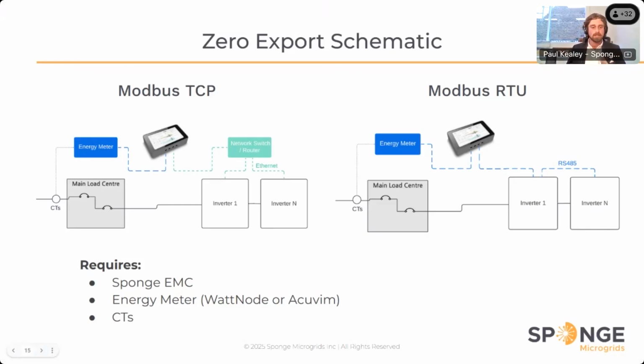There are several ways we can set these systems up. We have Modbus RTU and TCP communication capabilities available. We'll be doing a standard Modbus 485 setup for situations where we have 1 to 2 inverters that we're controlling. Anytime we go larger than that, with multiple inverter jobs, we switch over to a TCP converter to ensure that there's no delay in communications.